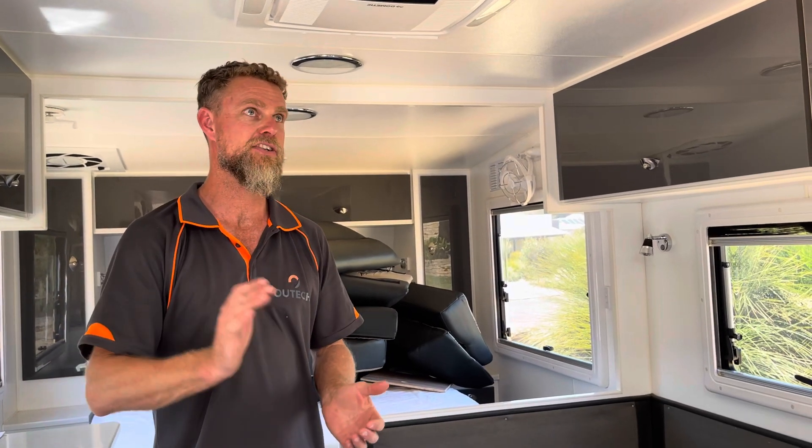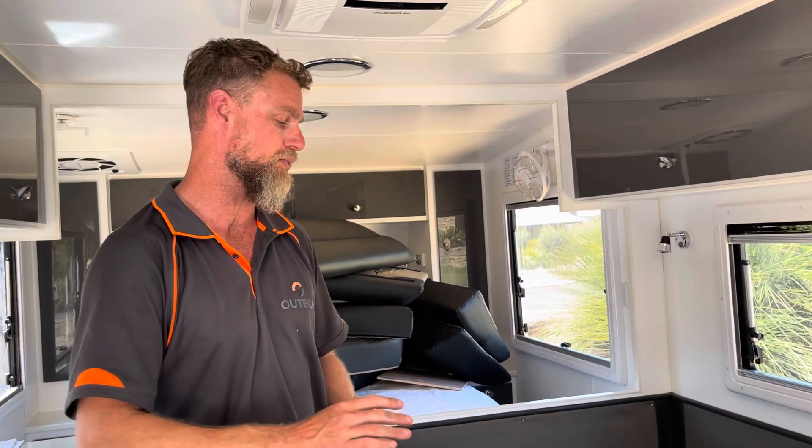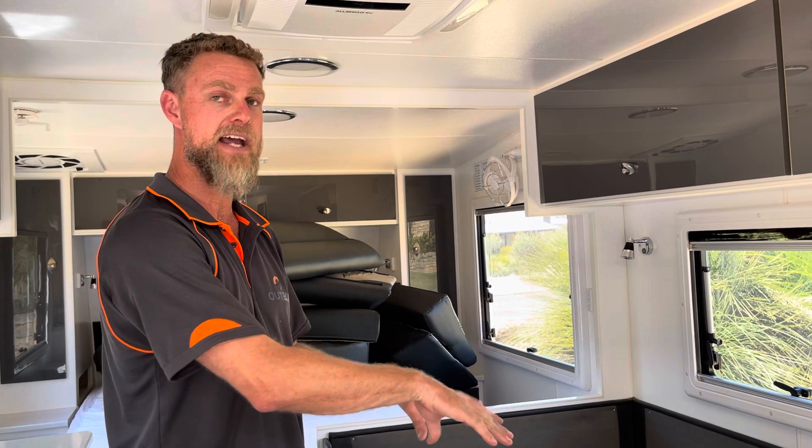This is a follow-up video relating to a particular caravan we talked about - the installation issues found whilst testing. Those installation issues included incorrectly cabled wiring from a cable size perspective, and also an incorrect pickup point location on the batteries.